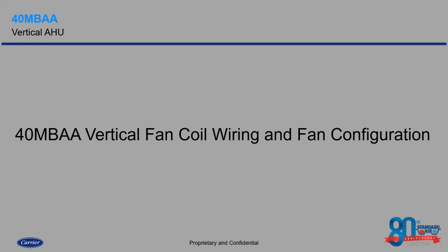So let's take a look at what it takes to wire up one of these, since we've discussed piping, and we now know that there is not a TXV removal kit that is required with this. All that we need to understand is that we have sweat connections, so we're going to have to braze, but when we are brazing, we need to make sure that we flow nitrogen to avoid any scale buildup that could clog strainers. So let's look at the wiring.